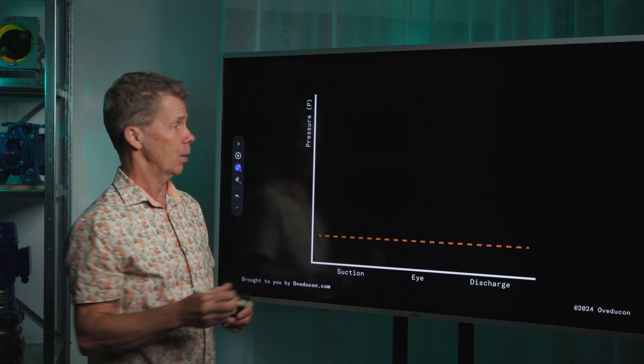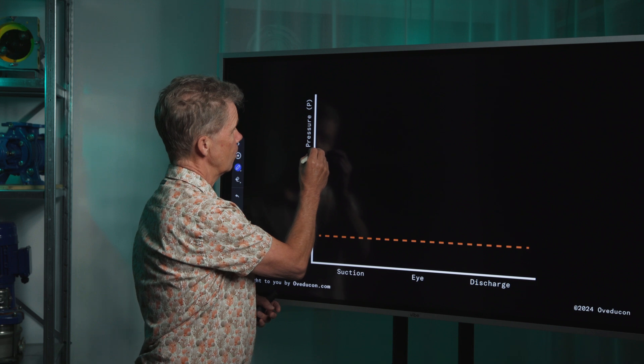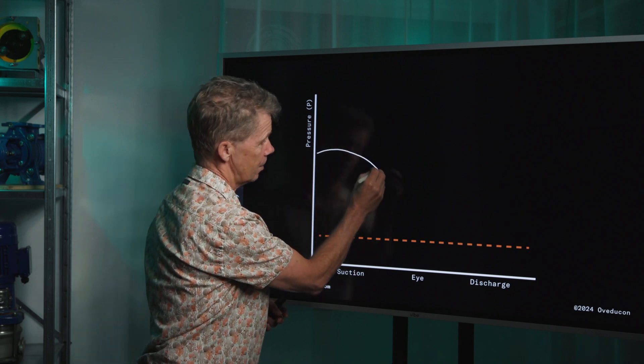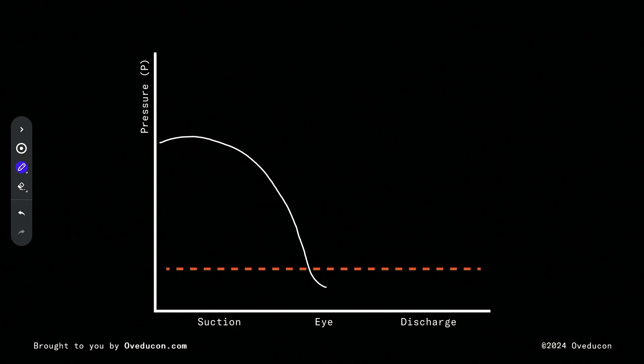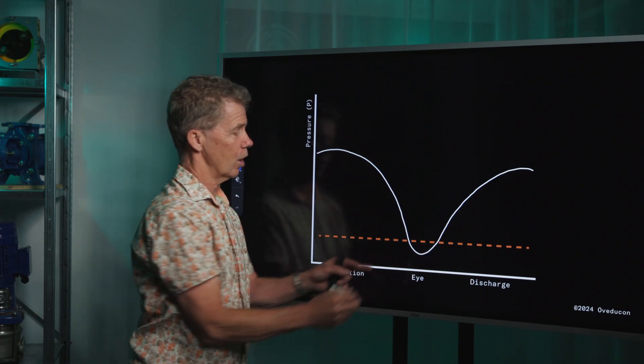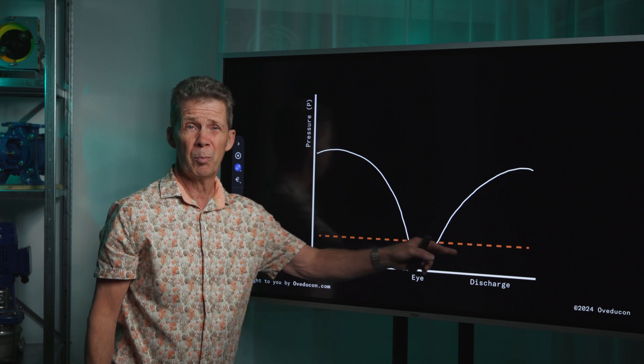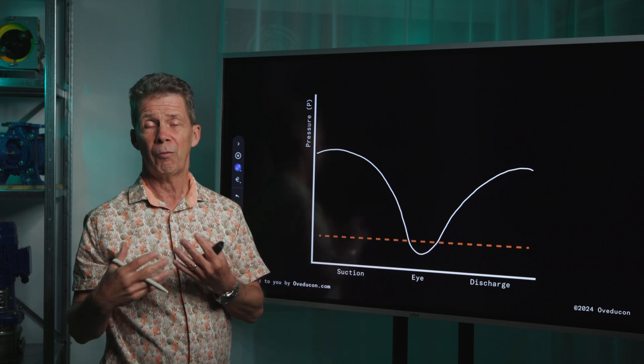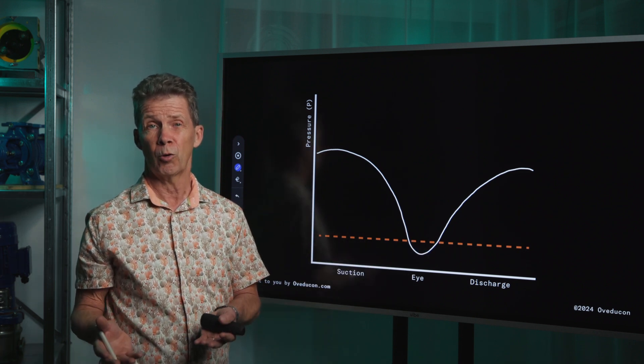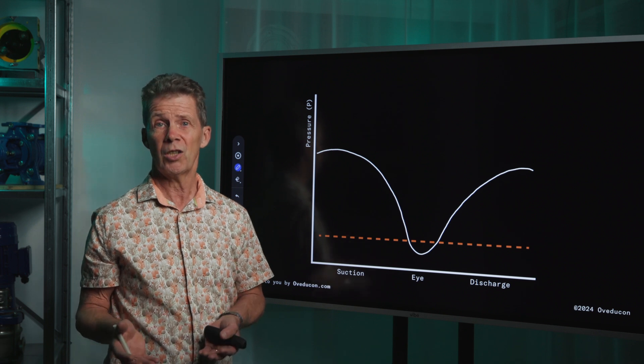But also another thing can happen. If you have a suction pressure line like this, the suction eye is coming below the vapor pressure line. Then vapor bubbles are formed and you will get cavitation. So we make an NPSH calculation to check if the NPSH available of the system is sufficient for the pump NPSH requirements.